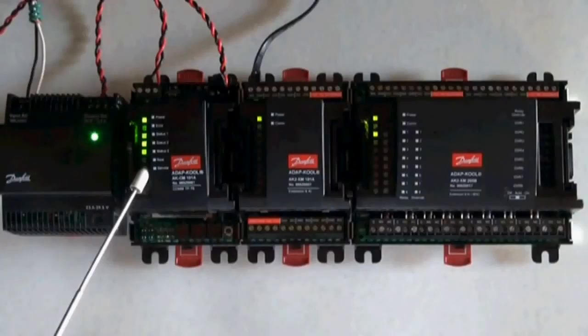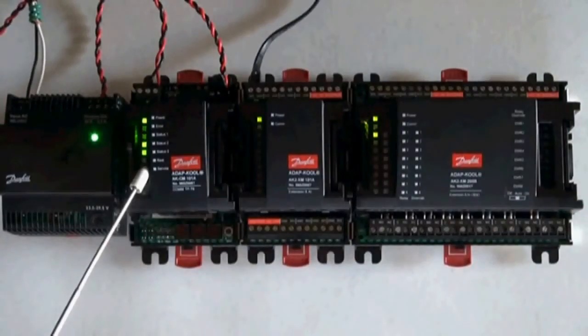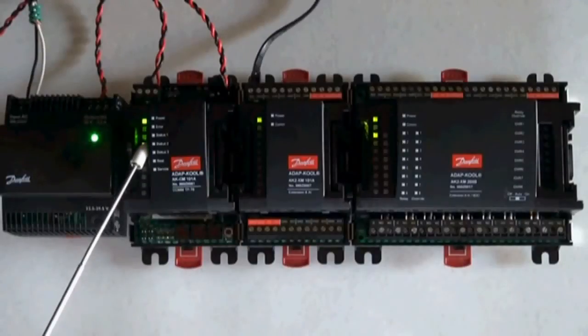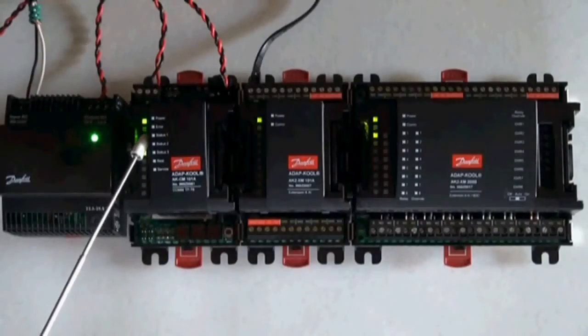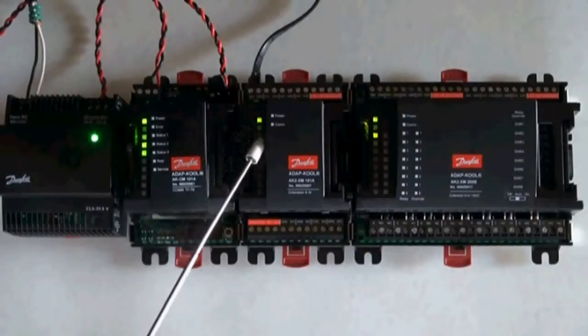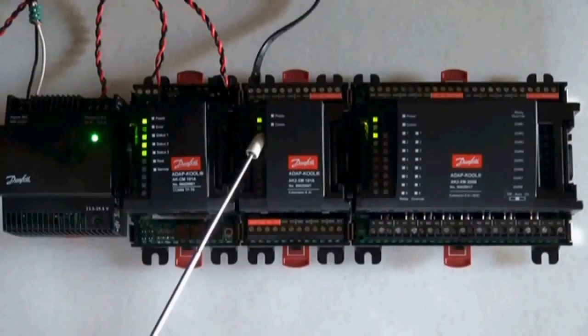Here you see the normal status has been restored. On the communication module, status 1 is again blinking and the error light is now out. On extension modules, the red COM light should be out to indicate proper communication.